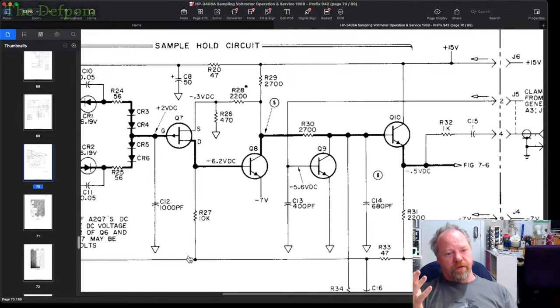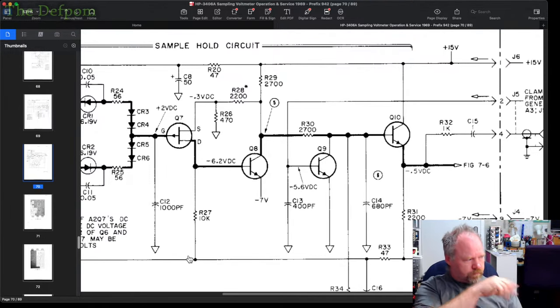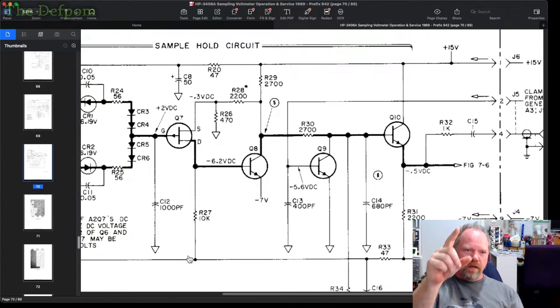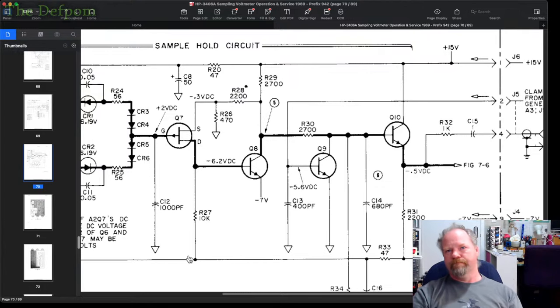I think they're referencing having the calibration point active, so it's getting the 1 volt RMS going into the probe. If I have that turned on or off, it makes no difference to the meter reading or to the voltages I'm reading on the unit. So it doesn't matter if I've got the signal on or off, the voltages stay the same, which is interesting. Apart from that 0.03 volt range, where I can get the meter to pop up when I turn the calibrator on. So that's another little clue which I haven't quite figured out the meaning of yet.